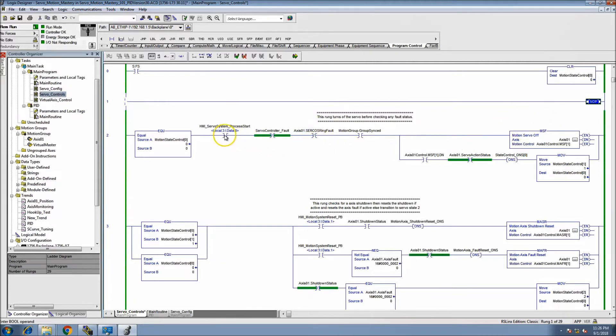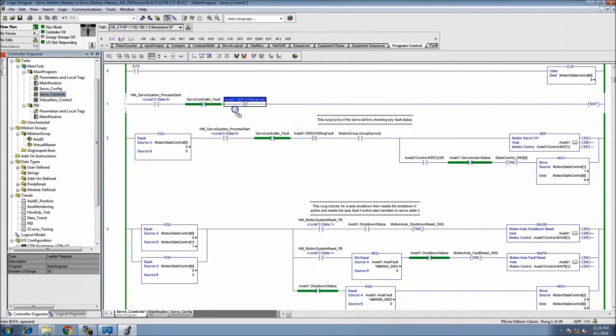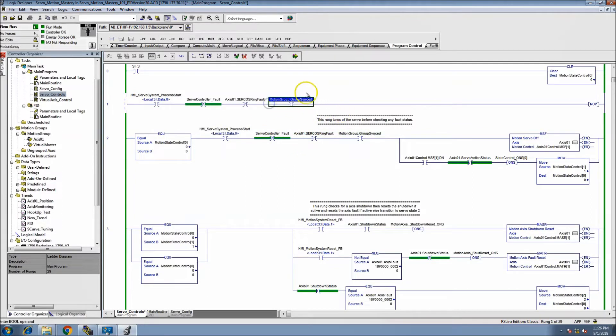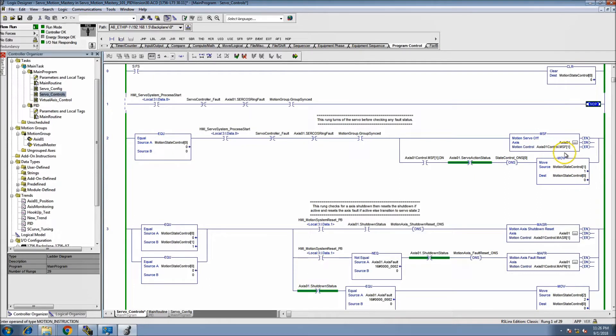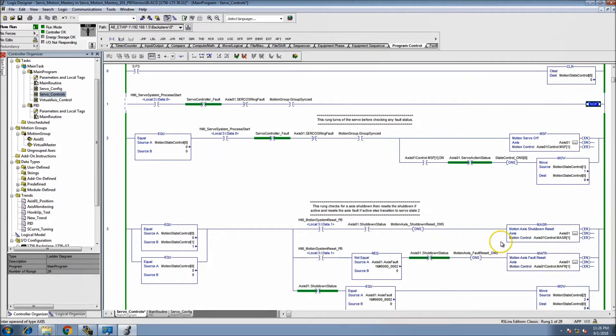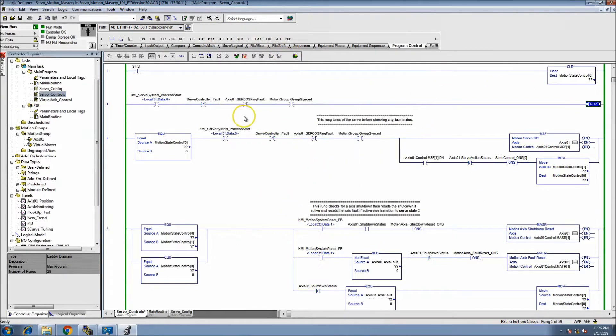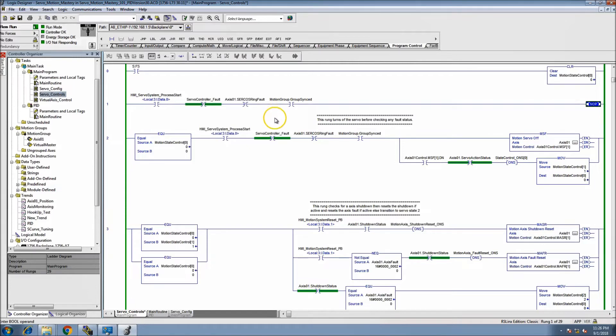Let's add a rung right here and use the NOP. If I wanted to use all these bits right here and just monitor them, I could do that and it will accept it because it doesn't need an operation on the backside. It doesn't need an OTE, clear, or any kind of instruction. You can simply assemble it like that, and these are just points of contact for troubleshooting methods.